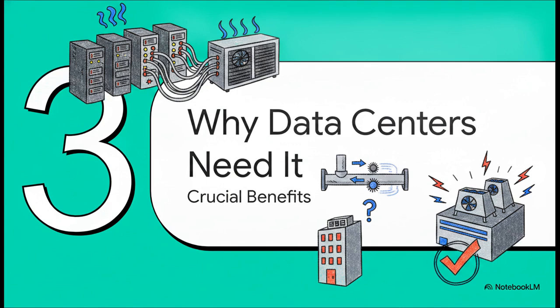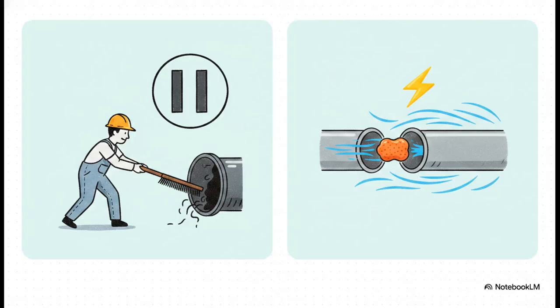Now, let's pivot to why this specific system is an absolute non-negotiable for modern heavy-load data centers. You see, standard commercial office buildings, they can usually afford to just pause operations in the winter for an annual deep clean. They shut off the chillers, and workers literally shove metal brushes down the tubes. But for a data center running ultra-high workloads around the clock, no way. Shutting down a massive chiller for days is way too risky. The heat buildup would be catastrophic. The ATCS completely solves this because it cleans while the machinery is running at 100% capacity. It guarantees true zero downtime operation.